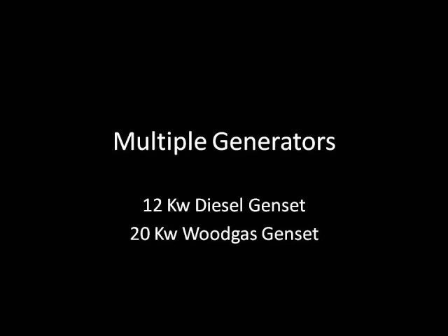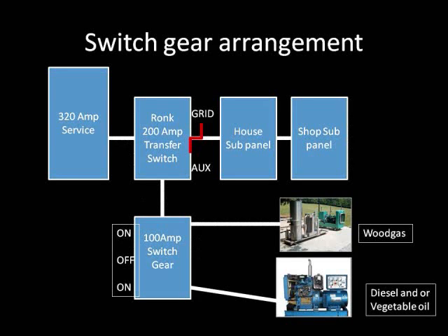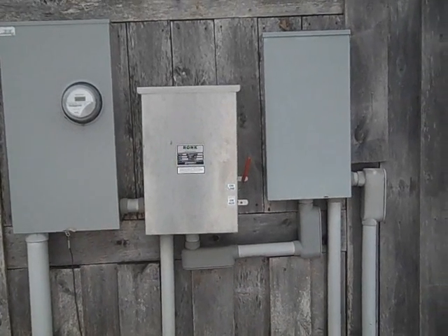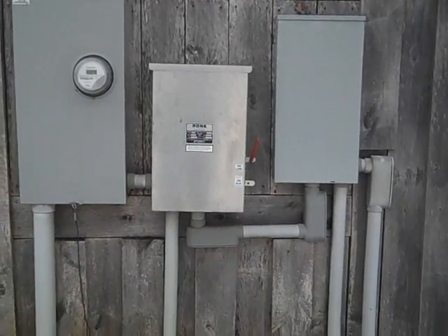We're going to be talking about multiple generators, running a diesel generator and a wood gas generator, not simultaneously, but one or the other, and what kind of switchgear would be needed to do that. This is if you have multiple generators or multiple inputs. Here's a slide of the arrangement of the switchgear required, and a couple of videos describing it.